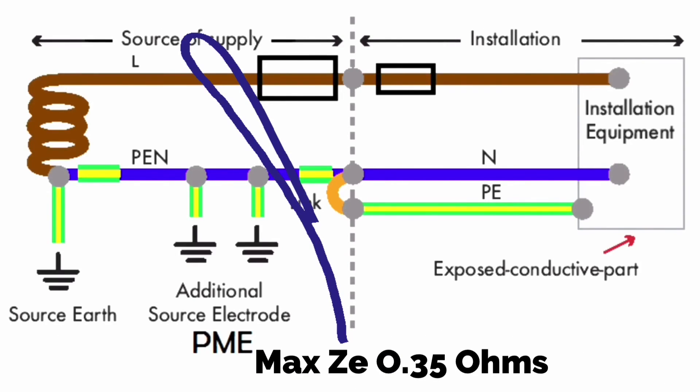The external earth fault loop impedance of the Supply Authority's cable is a maximum of 0.35 ohms. So to recap, whether Supply Authorities provide an installation with a combined Neutral and Earth or PEN conductor into the installation, the Earthing Arrangement is T-N-C-S. The Terra Neutral are combined within the Supply Authority's cable and then separated within the installation itself, making the Earthing Arrangement T-N-C-S.